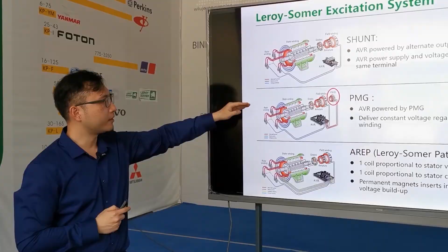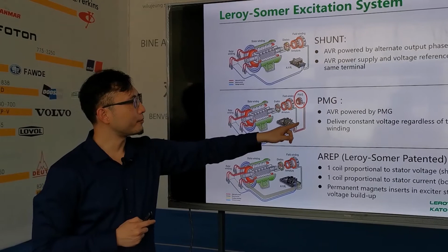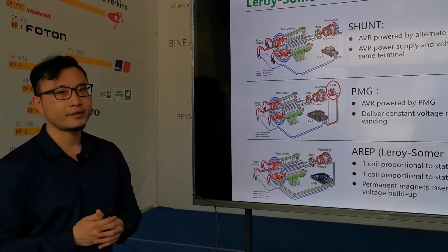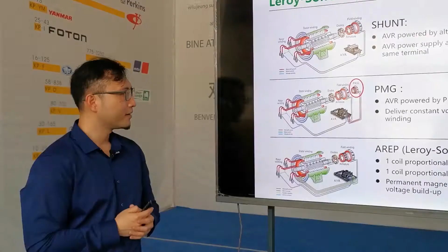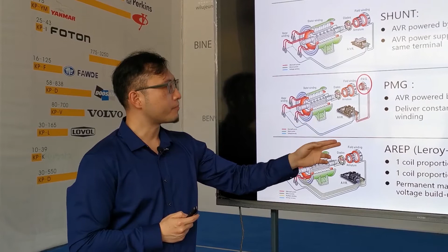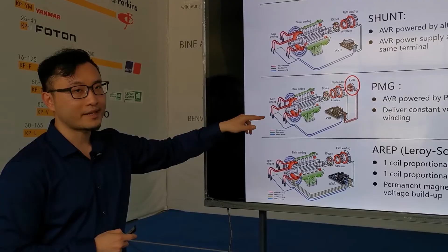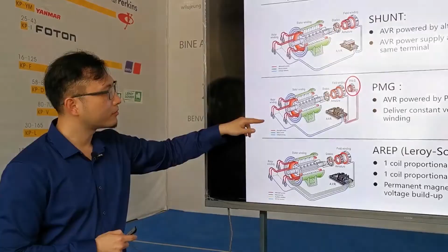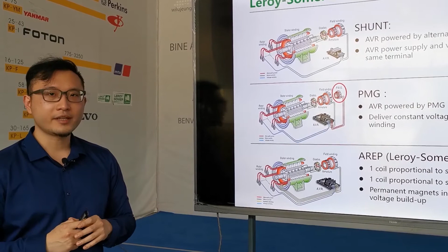And the second one, PMG. If we simply compare shunt and PMG in the picture, we can see that for PMG there is an additional part at the end of the alternator. It's a permanent magnet generator. It actually is a generator, and for PMG, the AVR will be powered by the PMG separately from the alternator. So imagine that if the alternator with PMG gets a short circuit, the phase voltage will be 0, but the AVR can still get power from the PMG. So normally we will say that an alternator with a PMG excitation system has short circuit current sustainability.